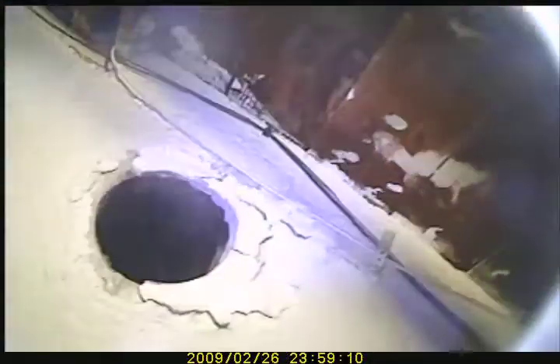Here's another pretty large gap. We are entering the thimble area. We have a 4-inch hot water heater and what I believe is a 7-inch boiler. The thimble area is about 3 feet long, with gaps at the thimble area itself. That concludes the video scan for today. This flue must be re-lined. Again, we are 30 feet tall.